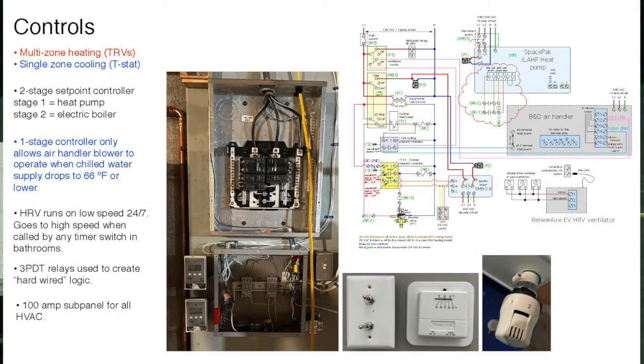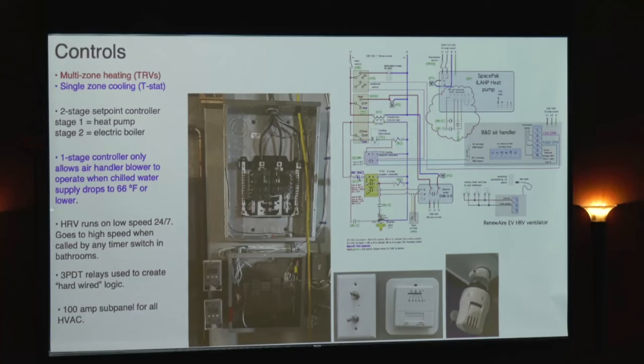The rest of the wiring, you've got a separate double pole. I think it's a 50 amp breaker on the heat pump. The electric boiler is double pole. I think that's a 60 amp breaker. The air handler is a 15 amp double pole. That's set up for 240 volts. And then there's one line voltage, 120 volt circuit that does the circulators. And there's a couple controls over on the side here, okay?